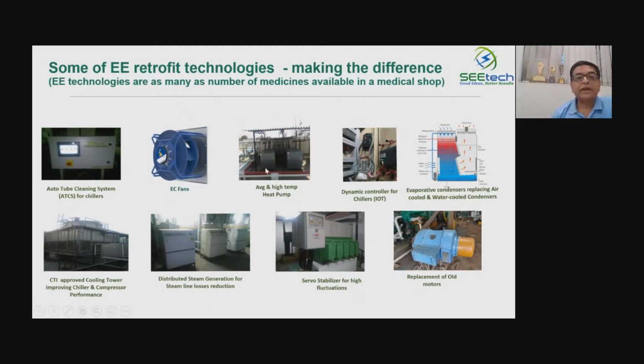Then we see heat pumps. Heat pumps, as compared to resistive heating, will give you phenomenal savings. But if you install a heat pump with a water side, then you get chilled water also, and this chilled water actually reduces the load on your actual chillers. So we strongly recommend that whoever has water cooled chillers in their facility should not go for an air source heat pump. They should go for a water source heat pump, so that whatever cooling your heat pump has produced gives you additional savings in your chiller.